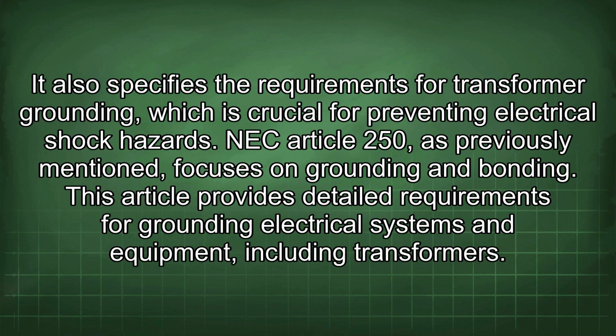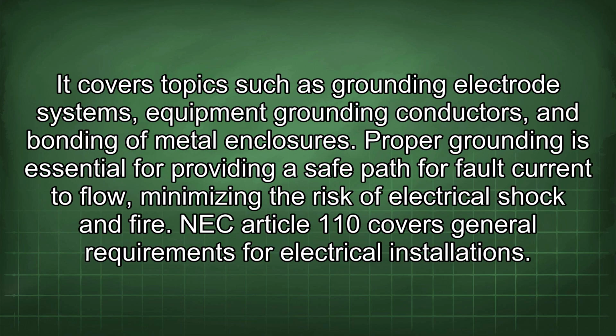NEC Article 250, as previously mentioned, focuses on grounding and bonding. This article provides detailed requirements for grounding electrical systems and equipment, including transformers. It covers topics such as grounding electrode systems, equipment grounding conductors, and bonding of metal enclosures. Proper grounding is essential for providing a safe path for fault current to flow, minimizing the risk of electrical shock and fire. NEC Article 110 covers general requirements for electrical installations.